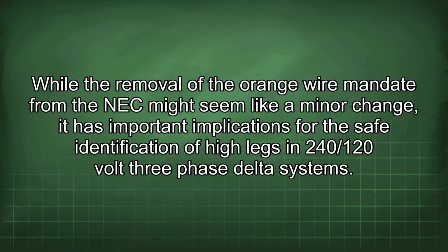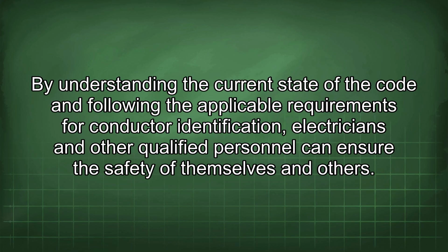While the removal of the orange wire mandate from the NEC might seem like a minor change, it has important implications for the safe identification of high legs in 240/120 volt three-phase delta systems. By understanding the current state of the code and following the applicable requirements for conductor identification, electricians and other qualified personnel can ensure the safety of themselves and others.